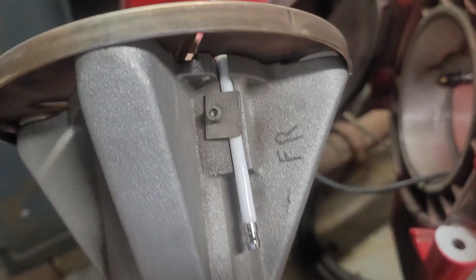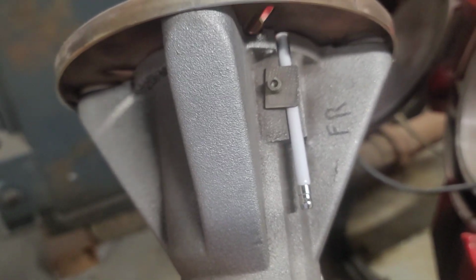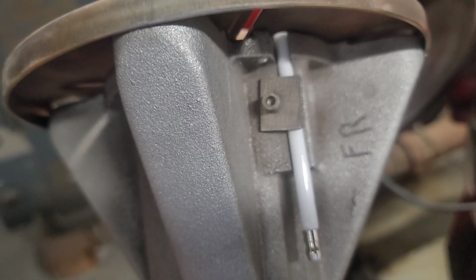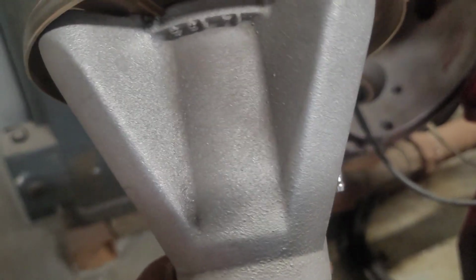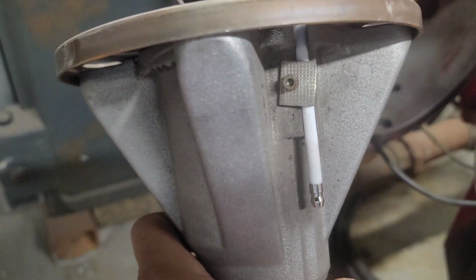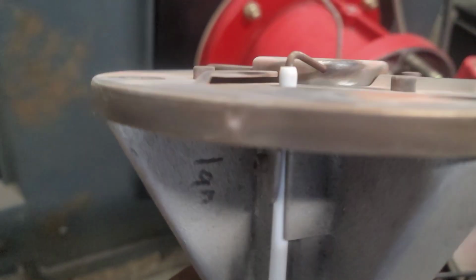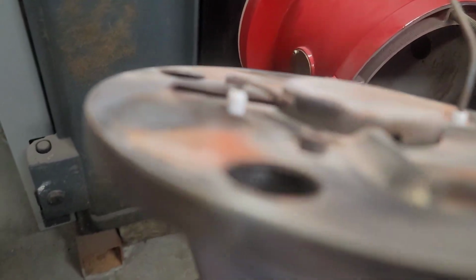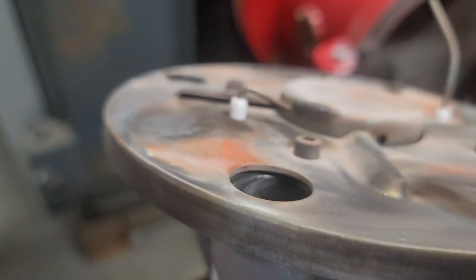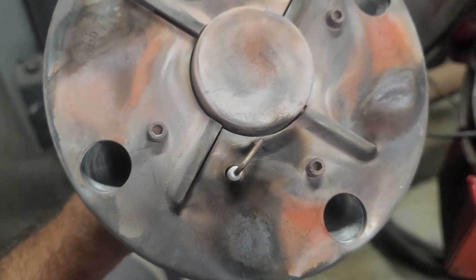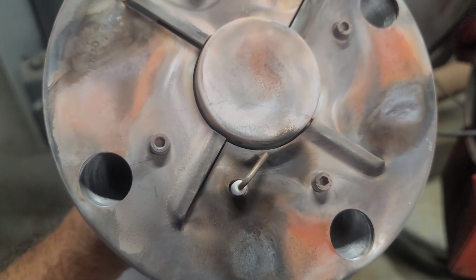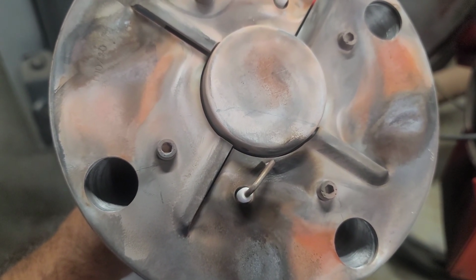Okay, so we can remove this flame rod and the igniter by undoing this Allen bolt. Same. And we also have to maintain the gap for the igniter. It should be 1/8 of an inch. I don't know if you can see that. It's not properly focused. Okay, so let's change everything.